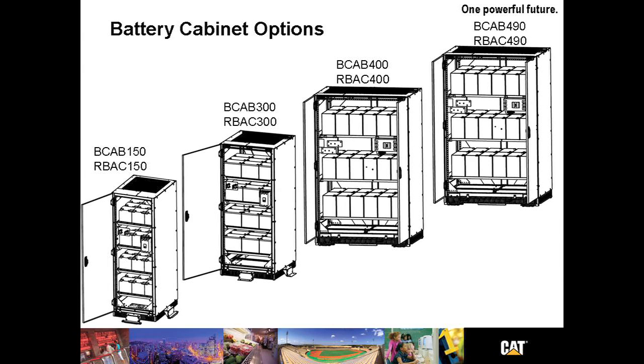Let's talk batteries and battery cabinets. Caterpillar offers both adjacent and remote battery cabinets. The adjacent battery cabinet provides a matching battery cabinet loaded with VRLA batteries for installation adjacent to the UPS. Connection cables to the UPS are provided with the adjacent, but not with the remote for obvious reasons. There's no way for us to predict how far the remote battery cabinet will be from the UPS. Each battery cabinet is provided with a battery disconnect breaker sized for the batteries provided.